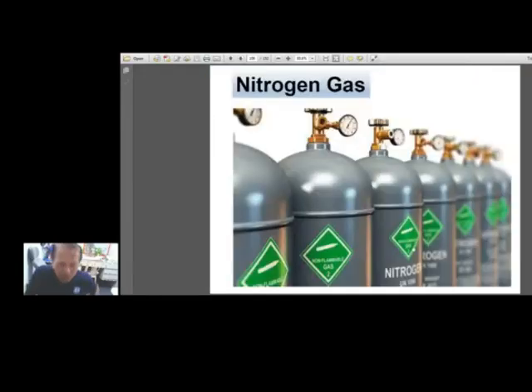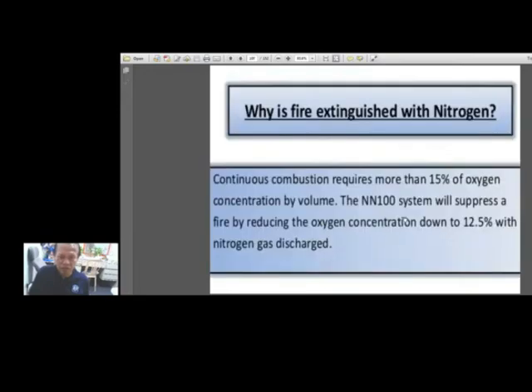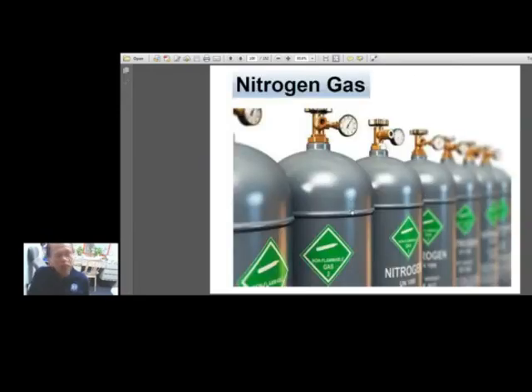Okay? So nitrogen gas can also be used. The air is 80% nitrogen roughly and 20% oxygen. Okay, so therefore nitrogen is plenty in the atmosphere. So you just need to produce nitrogen gas. You can also have equipment that can produce nitrogen at site, no? In other words, near the place of application, you can have equipment that produces nitrogen, which can already be injected to your room. But of course, it must be not occupied, because the moment you introduce plenty of nitrogen inside the room, then you are displacing oxygen. Okay?